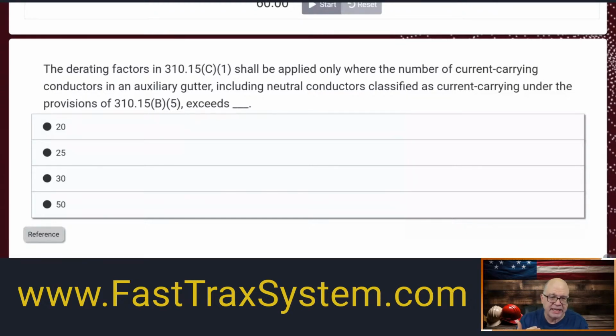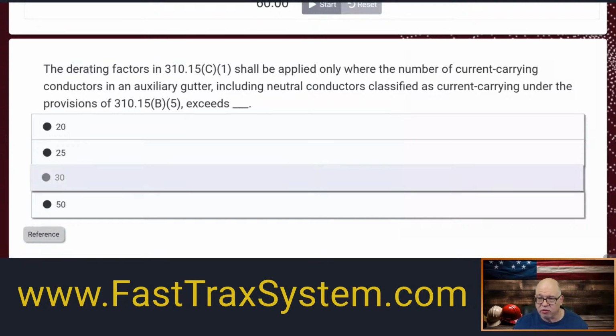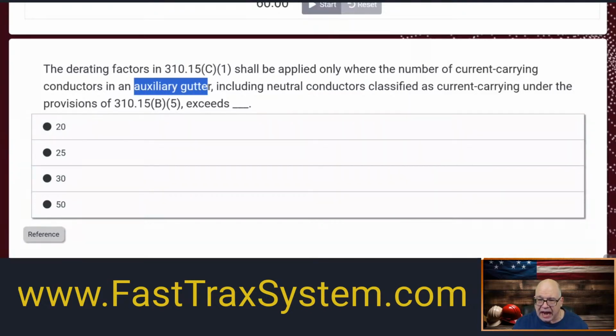But I'm in an auxiliary gutter, so the auxiliary gutter has other rules that you have to follow. And so you're saying, okay, well, where do I go for this one? Well, this is an example where you're not worrying about the rules actually in 310.15(C)(1), which is when you're dealing with more than 3 current carrying conductors, because this is specific to auxiliary gutters. And it would also be the same thing, by the way, for wireway. But here we're talking about an auxiliary gutter. So where do we want to go? Well, for me, I know that the auxiliary gutter is not a big article.